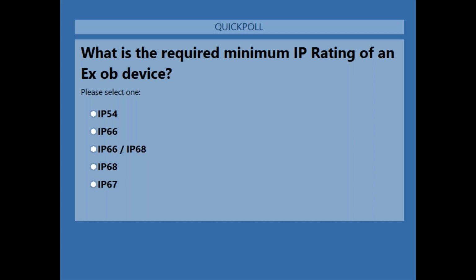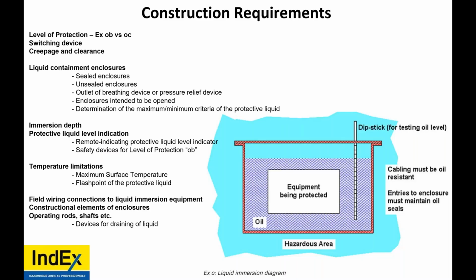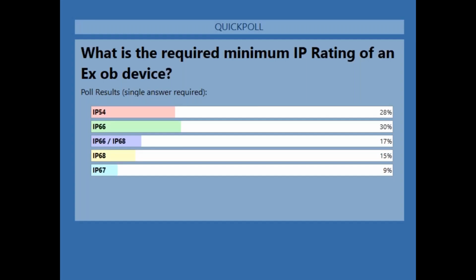Give another 10 seconds, we'll get about 62% voted. Okay. So the correct answer for Ex ob is minimum IP 66, meaning the answer cannot be 67 or 68. That is not a correct answer, because 67 and 68 do not give you 66. IP 54, remember, is only a minimum in the standard. If a manufacturer buys an IP 66 device and gives you an IP 66 gland, why are you invalidating their installation if you don't maintain IP 66?